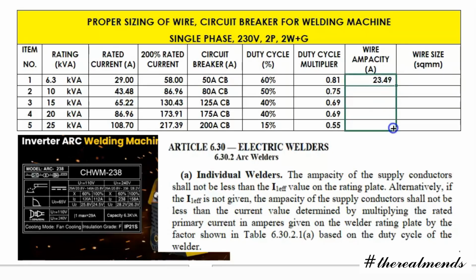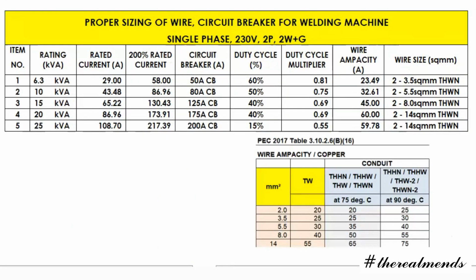And then you just drag this down to get the values for the next welding machines. After that, this is our reference for the wire ampacity, so for our wire size or conductors, from the PEC 2017, Table 3.10.2.6, B16. For the wire ampacity, we use copper. On the first column we have mm square, and then TW, THHN, THWN, THW at 75 degrees Celsius. So for our 6.3 KVA, we have a wire ampacity of 23.49 amperes. From this table, it pulls from here, 25. So our wire is 3.5 square mm.